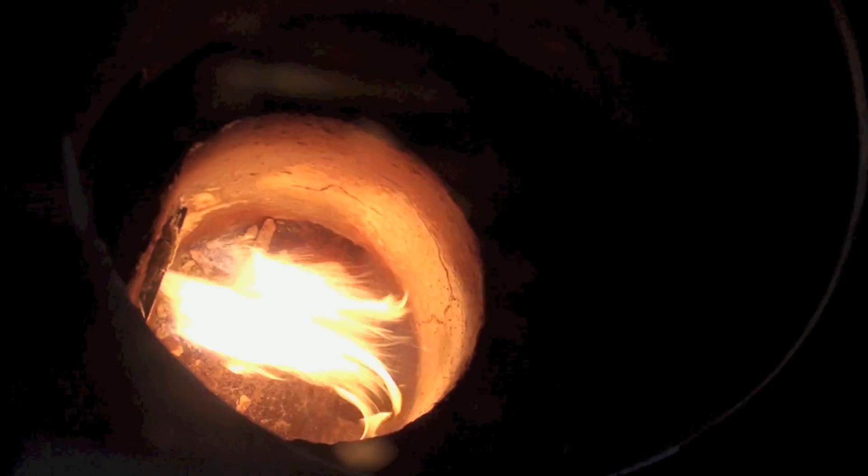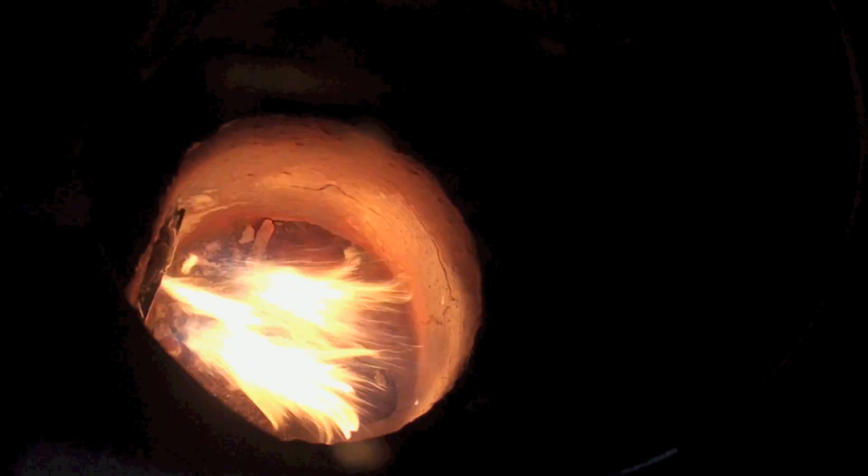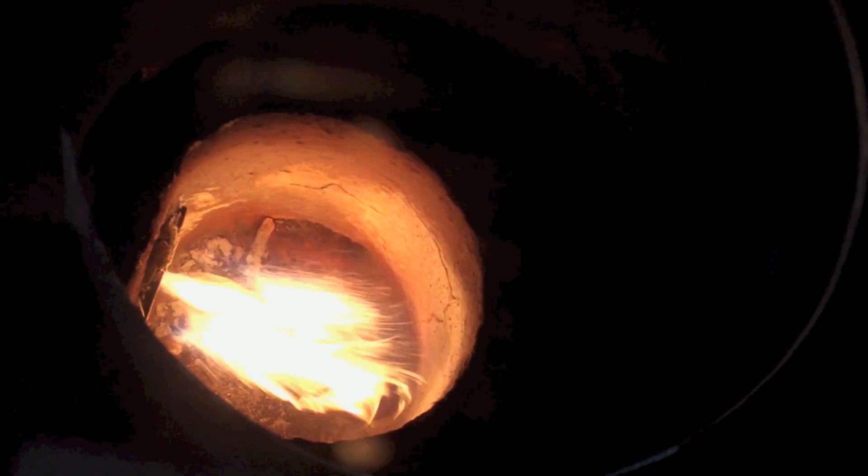This flame will not produce very much heat because there's way too much air coming in and it cools it down. It's extremely important on these oil furnaces that this area be hot. That's what that combustion chamber's for - it's supposed to heat up and glow and reflect heat back into the flame.